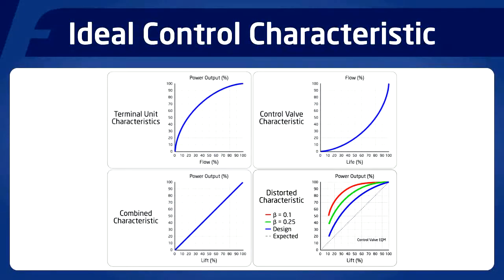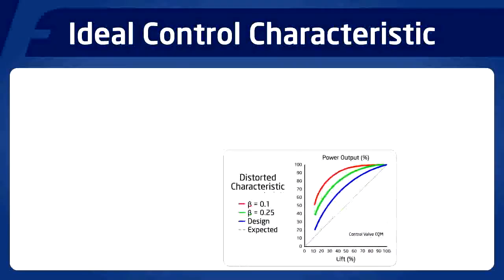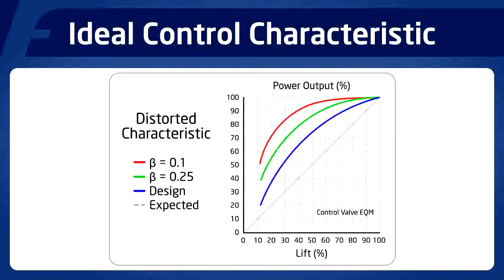However, the fourth factor is also important. We expect from the theory to have a proportional relationship between valve lift and power output. However, this is affected by the authority of the valve. Convention says we design typically for between 0.25 and 0.5 authority, which, whilst not proportional, is not bad.